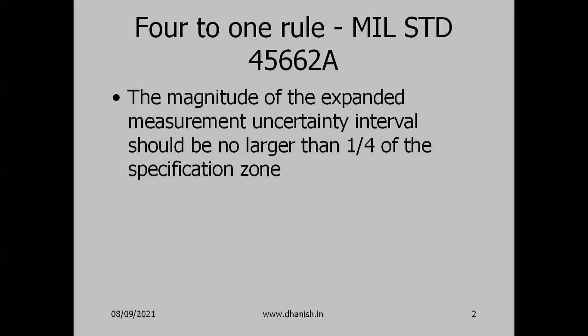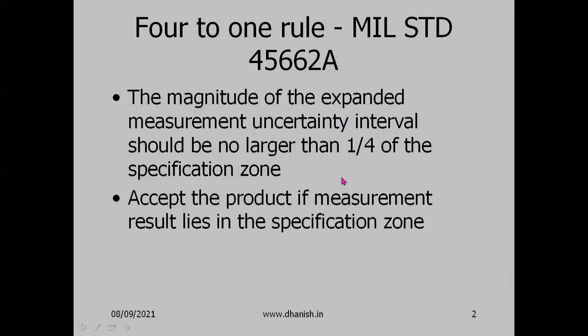The rule states that the expanded measurement uncertainty — the coverage interval — should not be larger than one-fourth of the specification zone. Accept the product if the measurement result (the average) lies within the specification zone; otherwise reject it.